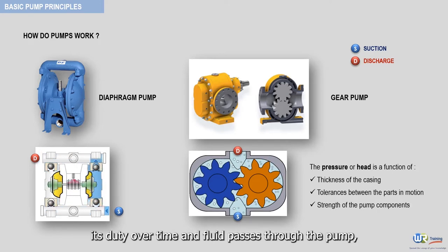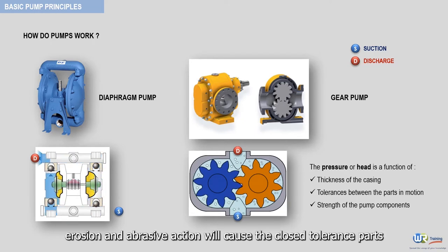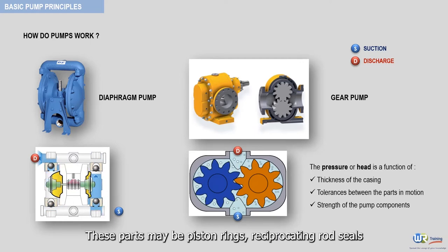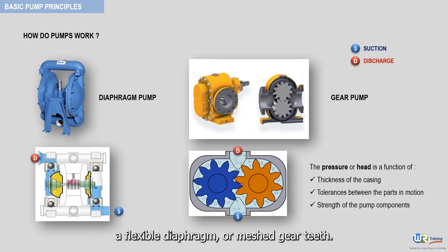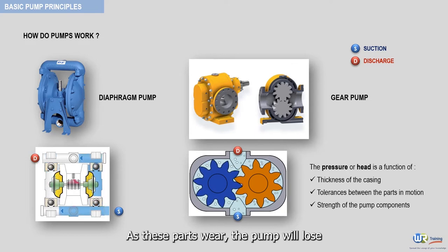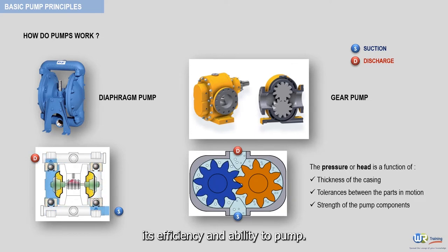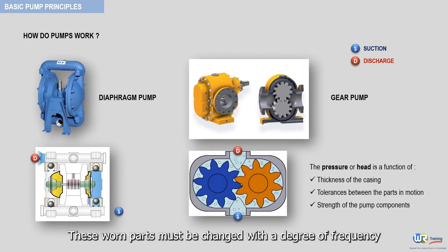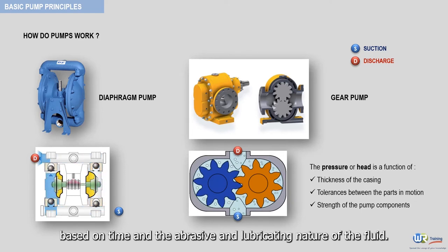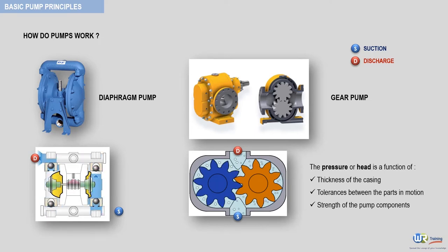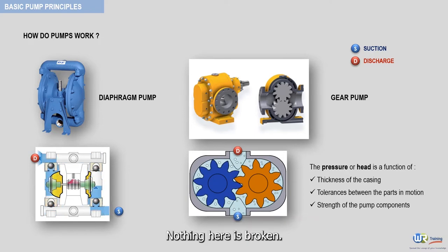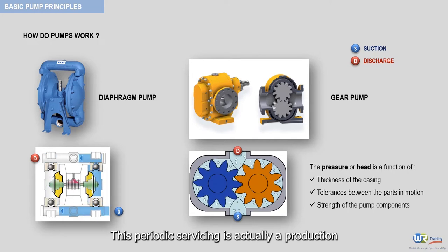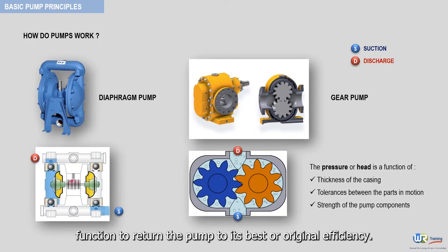As the pump performs its duty over time and fluid passes through the pump, erosion and abrasive action will cause the close tolerance parts to wear. These parts may be piston rings, reciprocating rod seals, the flexible diaphragm, or meshed gear teeth. As these parts wear, the pump will lose its efficiency and ability to pump. These worn parts must be changed with a degree of frequency based on time and the abrasive and lubricating nature of the fluid. Changing these parts should not be considered as breakdown maintenance — nothing here is broken. This periodic servicing is actually a production function to return the pump to its best or original efficiency.